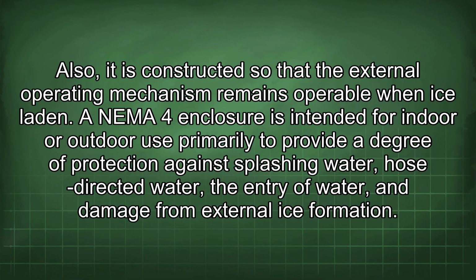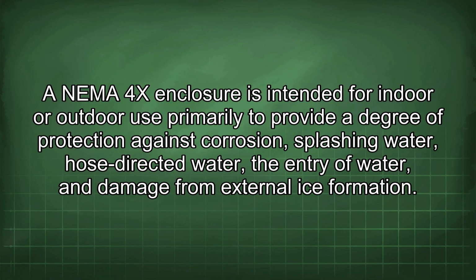Also, it is constructed so that the external operating mechanism remains operable when ice-laden. A NEMA 4 enclosure is intended for indoor or outdoor use primarily to provide a degree of protection against splashing water, hose-directed water, the entry of water, and damage from external ice formation. A NEMA 4X enclosure is intended for indoor or outdoor use primarily to provide a degree of protection against corrosion, splashing water, hose-directed water, the entry of water, and damage from external ice formation.